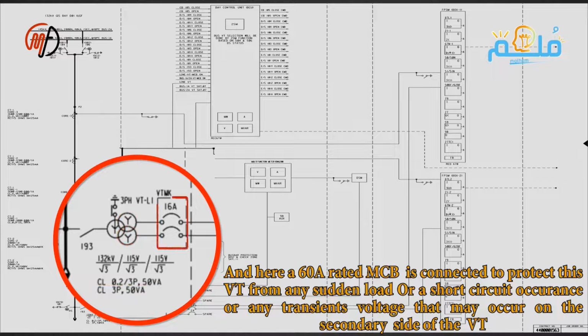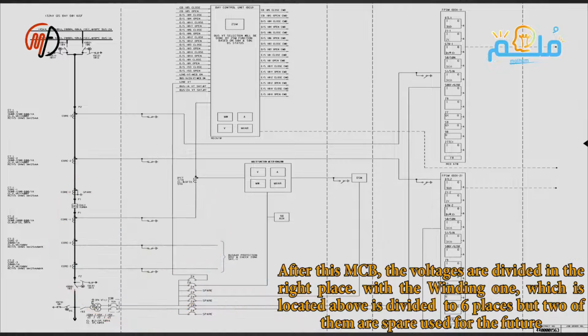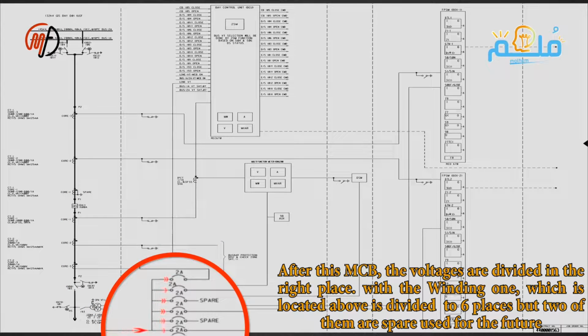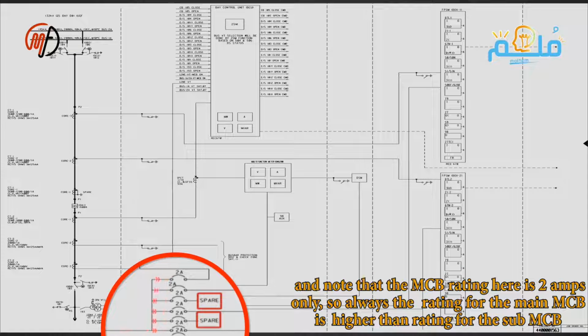Here we place a 16A MCB to protect this VT from any sudden load or short circuit in the windings, or any transient voltages that may occur on the side of the VT. After this MCB, the voltages are distributed to their appropriate places with winding 1, which is above, distributing to 6 locations, but 2 of them are spares for future use. Notice that the rated MCB here is only 2A. So the rated value of the main MCB is always higher than that of the sub MCB.